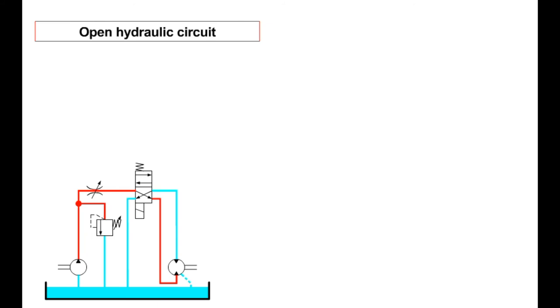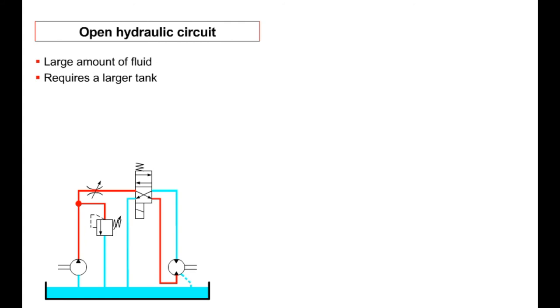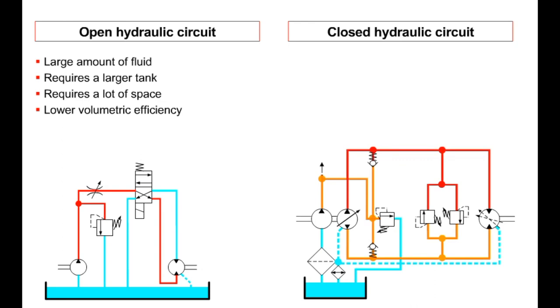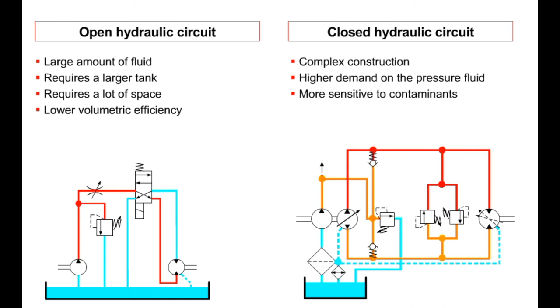In engineering there are no advantages without disadvantages. In an open hydraulic circuit, a large volume of fluid must be circulated, necessitating a larger tank and sufficient installation space, and the volumetric efficiency is less than in closed systems. A closed circuit requires more complex construction — for example, an additional feed pump is necessary. Since pressure fluid is supplied directly from the consumer back to the pump, it has little opportunity to cool, leading to strong operational demands on the fluid. Furthermore, contaminants taken up by the pressure fluid may enter the hydraulic pump.